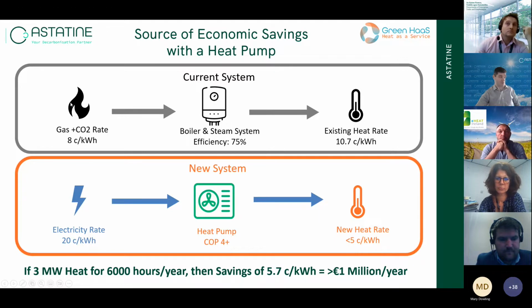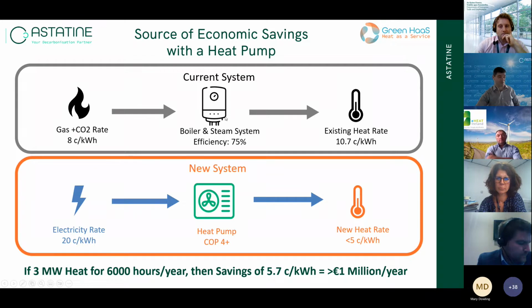We're looking at what your current fuel rate is. So let's say in this particular case, we have a fuel rate of 8 cents a kilowatt hour. I'm sure many of you are thinking we'd love to have a fuel rate of 8 cents a kilowatt hour right now. It's probably something much north of that if you're looking at a bill from the last month or two. What's the efficiency of your boiler and steam system? So not just the boiler producing the steam, but then distributing the steam around the plant. Using that efficiency, dividing your fuel rate by your efficiency, you get a heat rate. In this example, it was just under 11 cents a kilowatt hour.